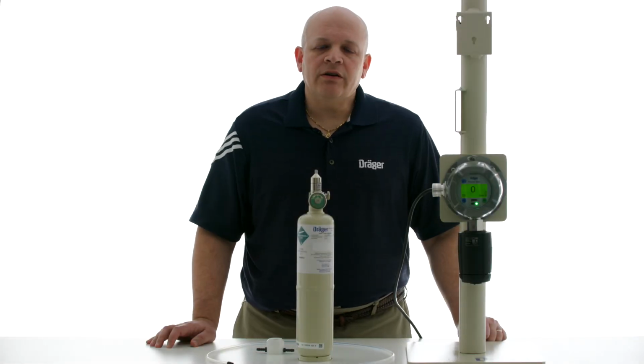Hi, I'm Steve from Draeger, and I'll be showing you how to calibrate an electrochemical sensor using a Polytron 8100. The procedure is virtually identical if you're using a Polytron 7000 or a PointGard 2100. You will need a zero gas and also a span gas.